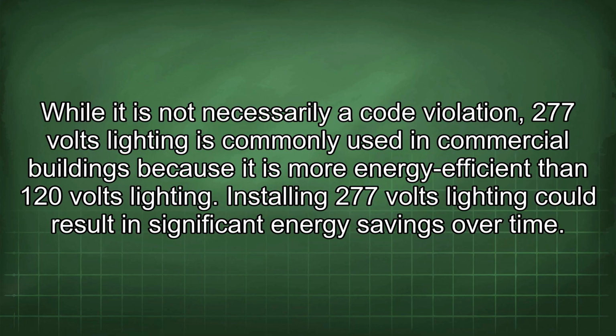While it is not necessarily a code violation, 277 volts lighting is commonly used in commercial buildings because it is more energy efficient than 120 volts lighting. Installing 277 volts lighting could result in significant energy savings over time.